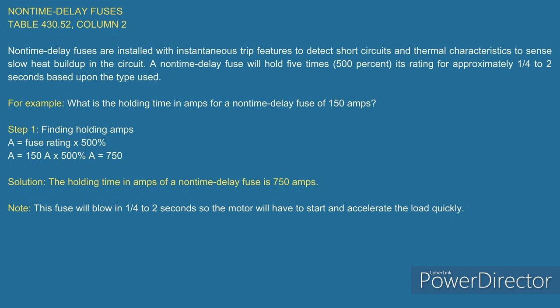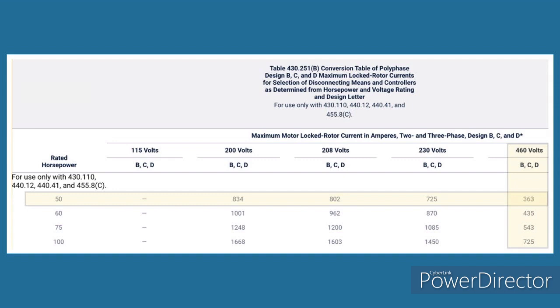Okay, now I want to show you something here. That's just a basic thing that we tie in, and I want to show you things that you get into. Now, this next one, I'm going to give an example to tie all this in. We're going to have an illustration, and we're going to talk about a 460 volt, 50 horsepower, three phase motor. And when you look at this motor, you're going to see that in table 430.251B, it's going to tell you that the locked rotor current here is 363 amps. Okay. Now watch this. All this that we're showing you is just to prove what they used to do back in the day. When they started designing these tables and everything, this is how they knew that they had a proper size overcurrent device in order to provide protection for the inrush current of that motor.